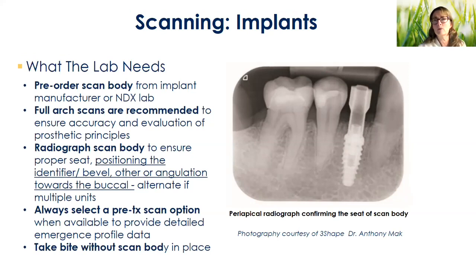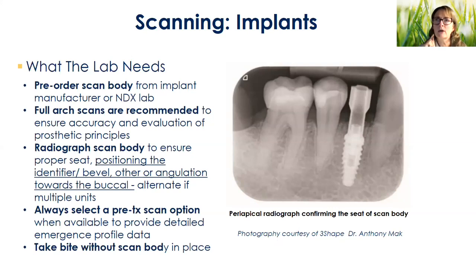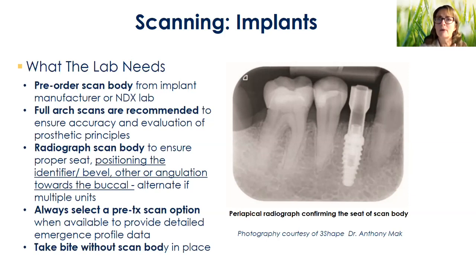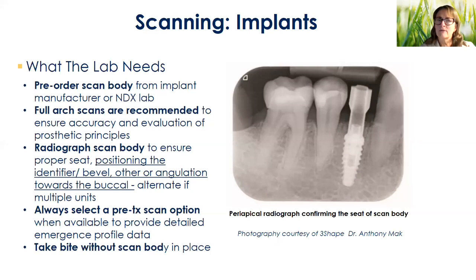Every scan body has what we refer to as a key identifier — that might be a bevel, a divot, or some sort of key angulation. Do your very best to place it so it's facing buccally. If you have multiple units in a row, alternate: key identifier buccally, then lingually, then buccally, then lingually. Please don't try to use the same scan body and move it from one tooth to the next, or keep them all facing buccally. The scanners are really smart, but they're not smart enough to realize sometimes that it's an identical part, and it tends to get stuck and doesn't stitch the data together very well.